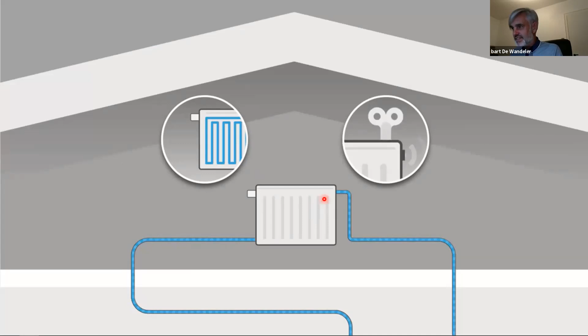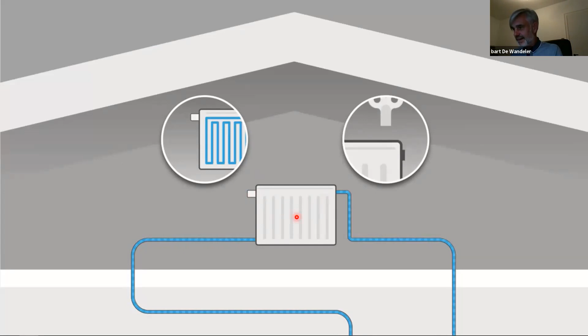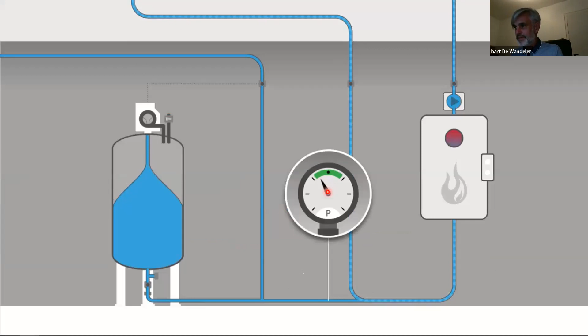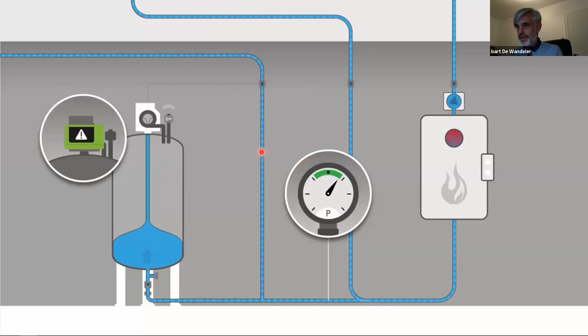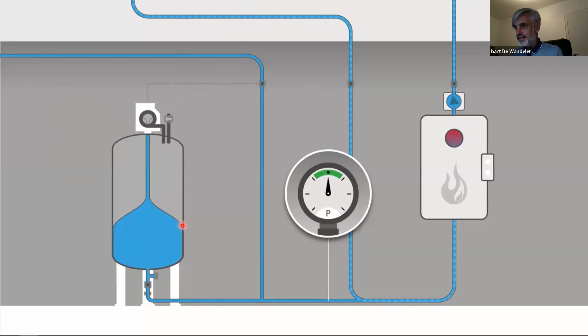For example, if somebody degasses a radiator above in an apartment, you will see that the control of it is really nice, because when we scroll down now, you will see that the pressure is relieving because we make space, we relieve air. So because we have done a small degassing above, the system will detect this and will automatically put water back to make sure that above we have no negative points in the system. Also, when the volume is getting critical, we open a water makeup and we will start to fill to make sure that the water reserve in your expansion tank is always perfectly controlled. So you don't have to fill by hand, it is all done automatically.